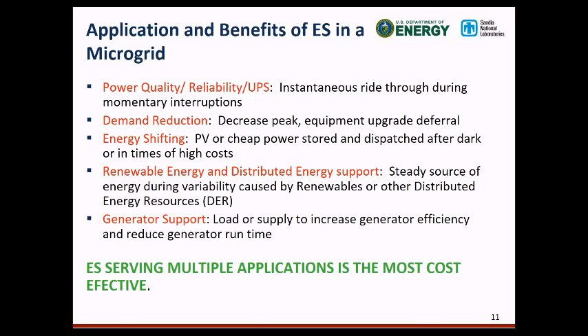So what I say is, hey, listen, if you're going to do a project and you're going to install a UPS — and by UPS I mean, in my definition, a unidirectional inverter, meaning power only flows toward the load, it doesn't go back to the grid — maybe look instead at an energy storage system, which is a bidirectional inverter. Power can go to the load or back to the grid. That's a very high level analogy, but basically that's how it works, and maybe you could utilize that energy storage system.